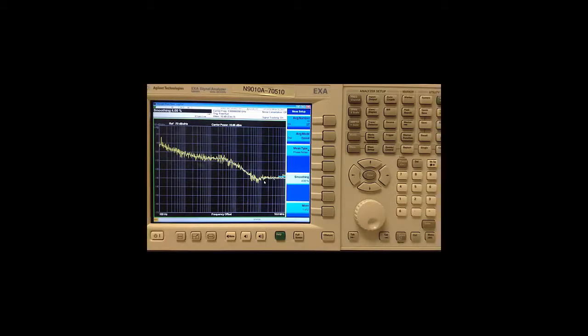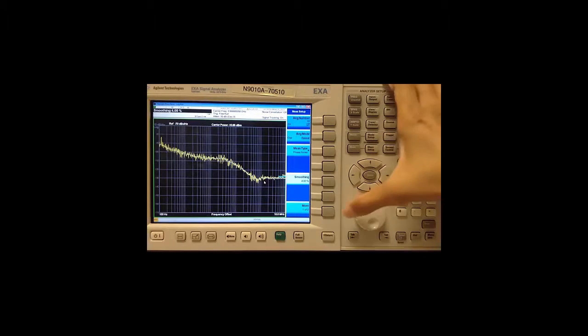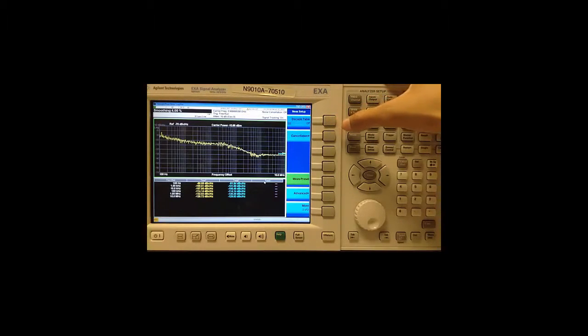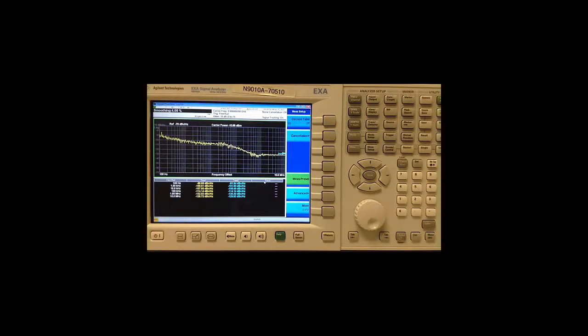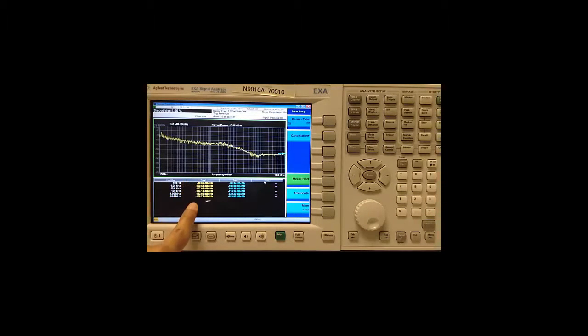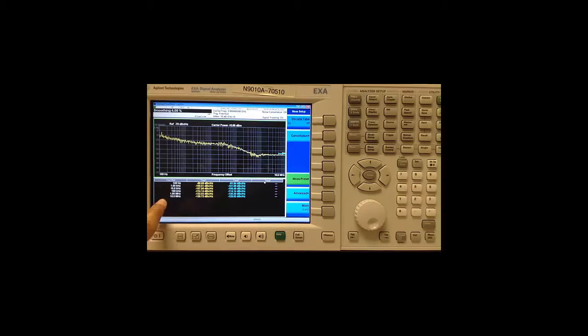I can also get a tabular view of the various decades by going to measure setup, more and decade table on. This shows me my power spectral density values from the raw trace as well as the smooth trace versus the actual offset frequencies.